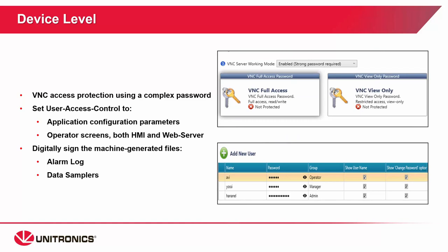VNC is a virtual network connection — it allows you to view the screen remotely when set to server mode. The new UniLogic will require a password when VNC is enabled. We do recommend a complex password so that your HMI is remotely protected. User access control manages HMI users. You can assign different levels to users and assign them to different groups with different permissions on the HMI, which will protect against any accidental HMI interaction. There are also users and passwords on the web server — if a web server is enabled, we recommend utilizing that functionality.